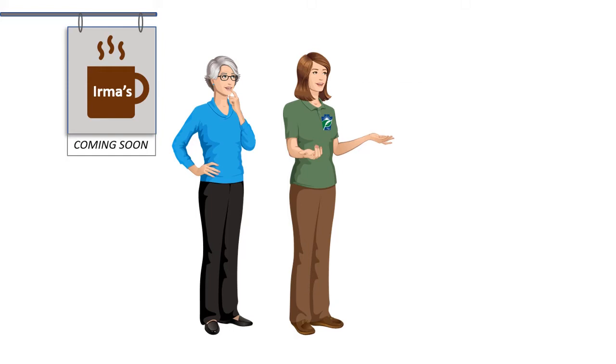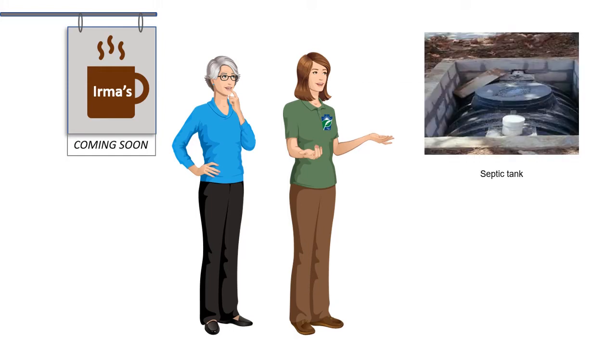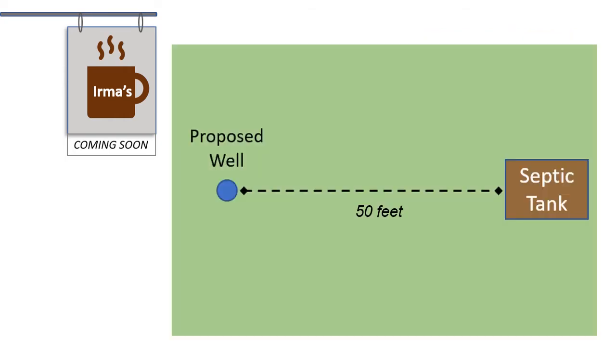For example, the well must be drilled far enough away from any potential sources of contamination to minimize the risk of contaminated water reaching the well. The required distance between the well and a potential source of contamination is called the setback distance, and there are different required distances depending on the potential source of contamination.